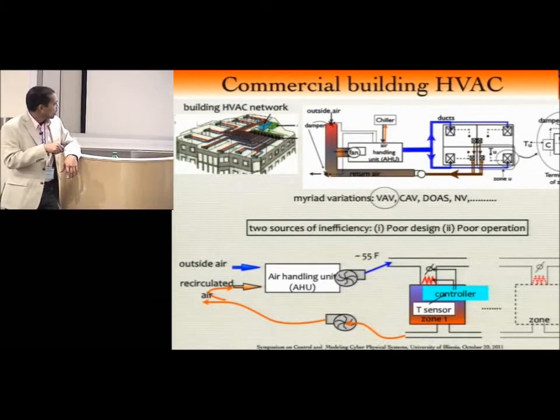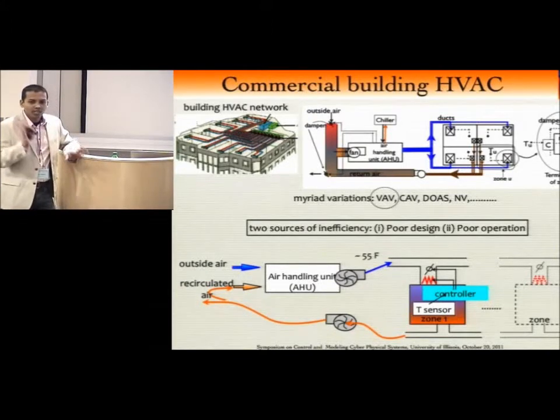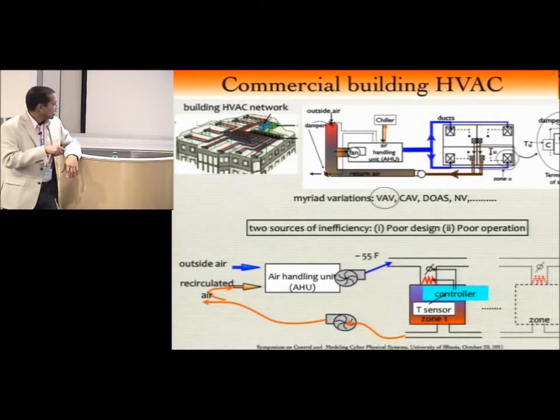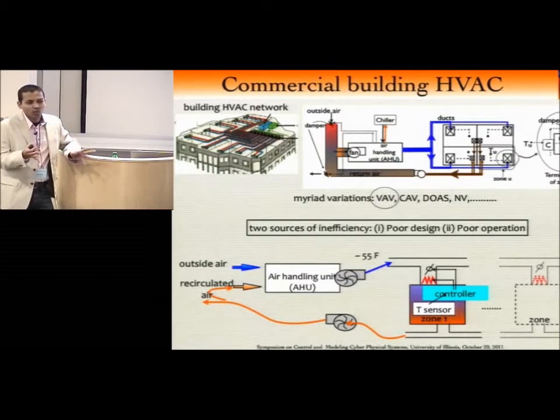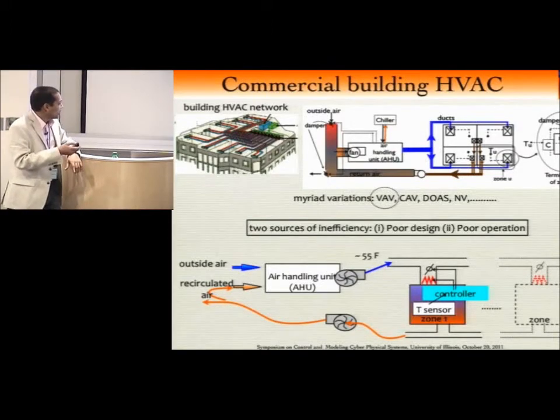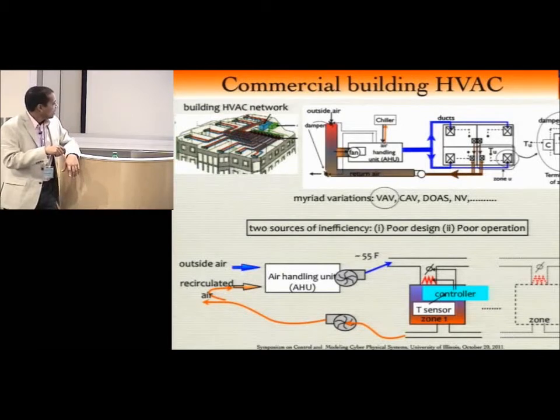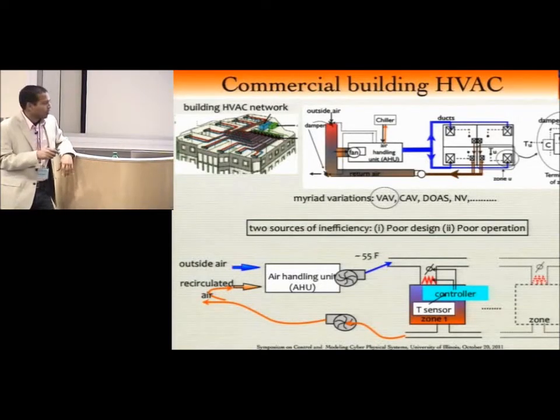That particular controller at every zone is completely decoupled, so every zone is controlled independently, and that controller controls the flow rate through something called a damper. I don't know why it's called a damper, but that's the industry name for it. It controls the flow rate, and then there's another reheat coil which can either reheat the air or not reheat it basically, right? And all that air is flown back and all that. So there are several sources of inefficiency in this whole process, but the two main ones are design and operation.